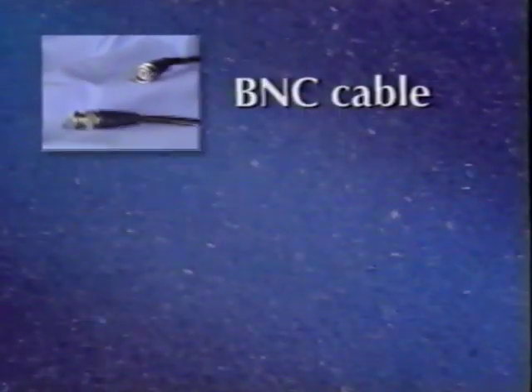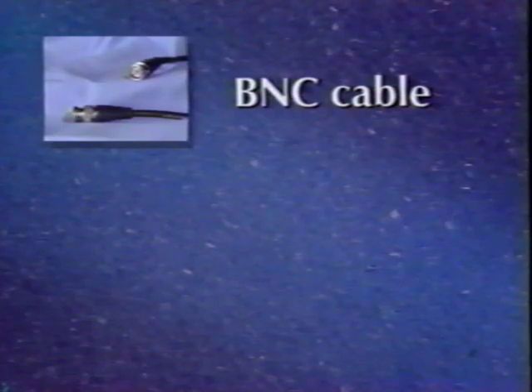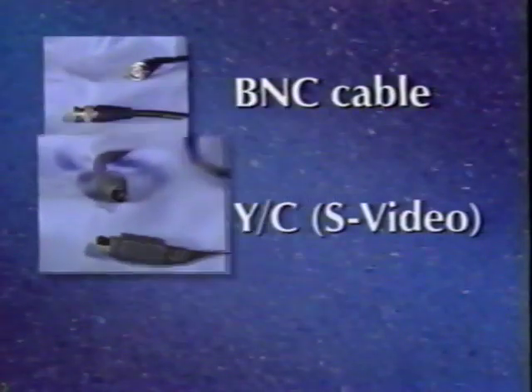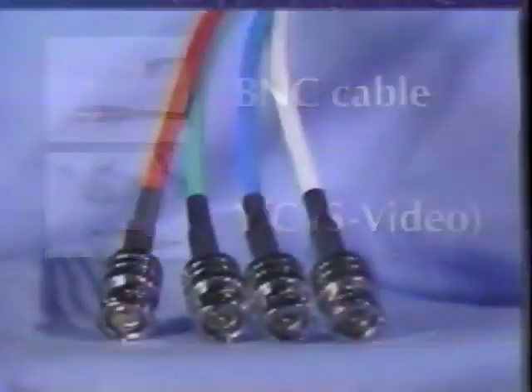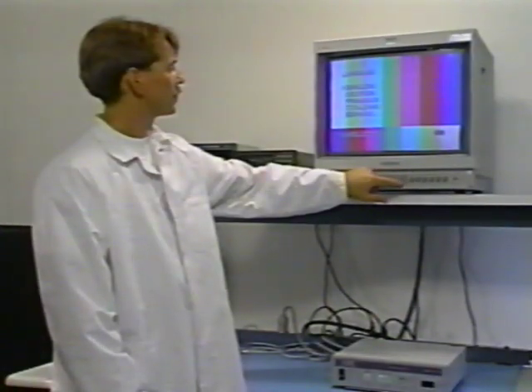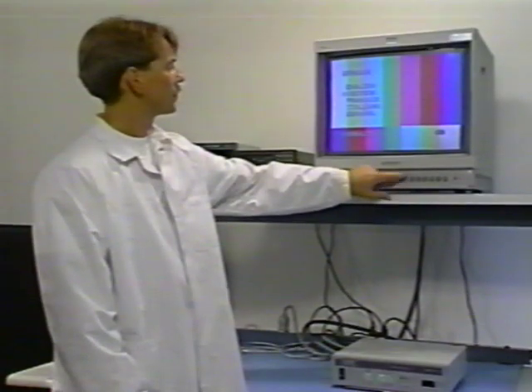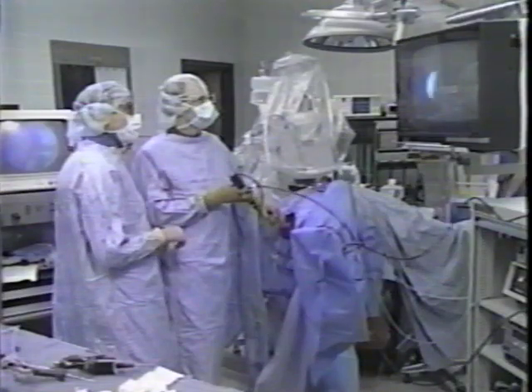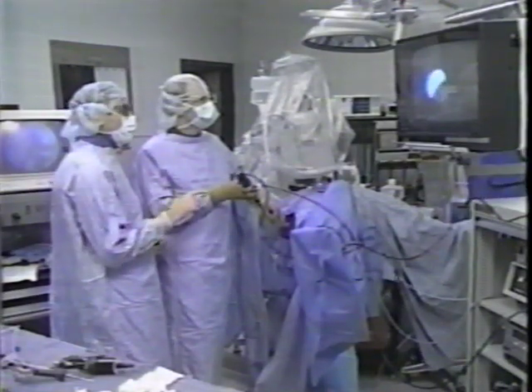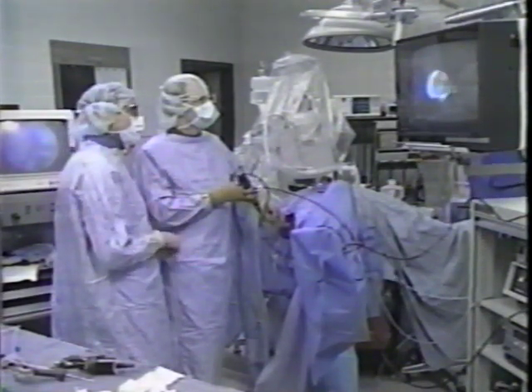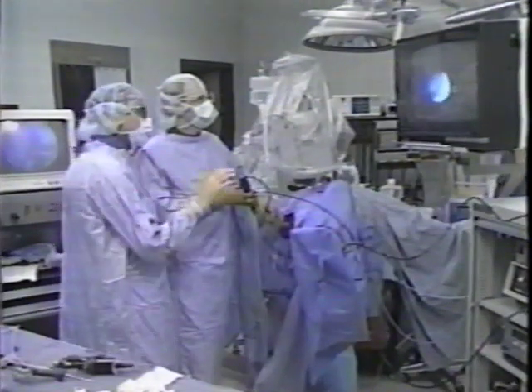The CCU is connected to the video monitor by a standard BNC cable, YC or S-video cable, or an RGB cable. Monitors vary from manufacturer to manufacturer, and it's a good idea to familiarize yourself with the menus and functions of the monitors being used with the endoscopic system. Every piece of equipment in the system can affect the image the surgeon relies on to perform endoscopic procedures.